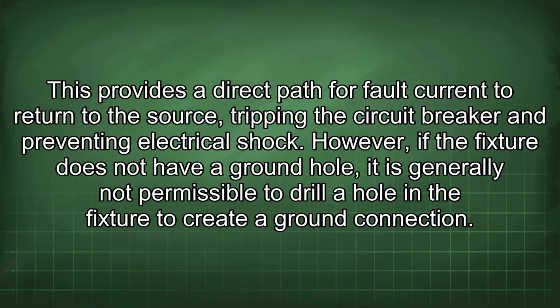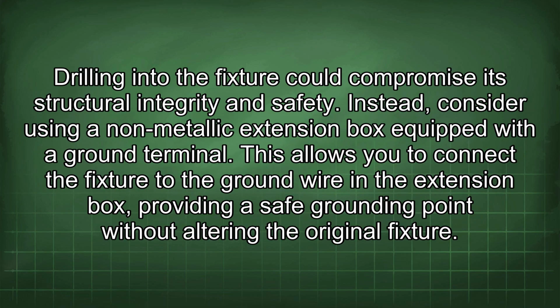However, if the fixture does not have a ground hole, it is generally not permissible to drill a hole in the fixture to create a ground connection. Drilling into the fixture could compromise its structural integrity and safety. Instead, consider using a non-metallic extension box equipped with a ground terminal. This allows you to connect the fixture to the ground wire in the extension box, providing a safe grounding point without altering the original fixture.